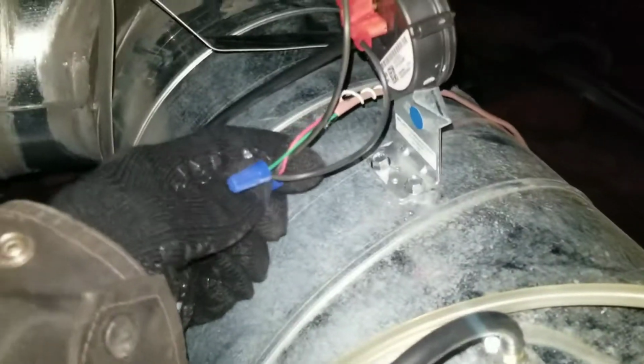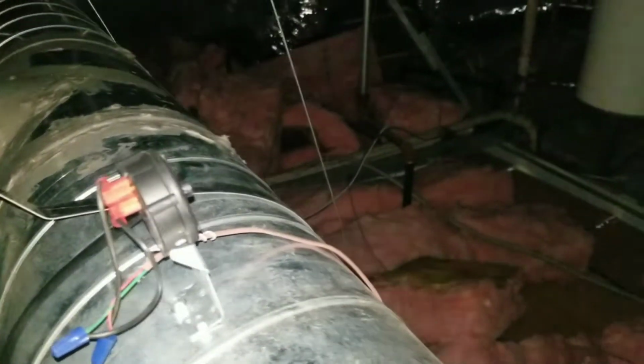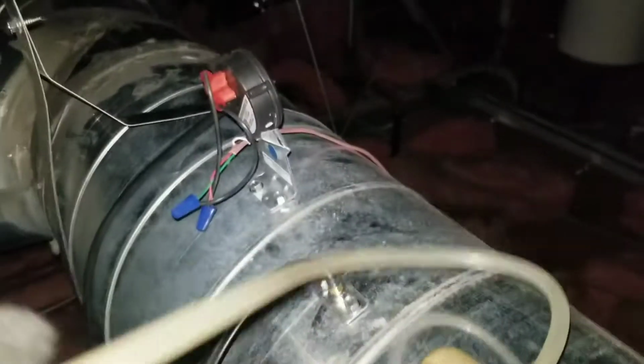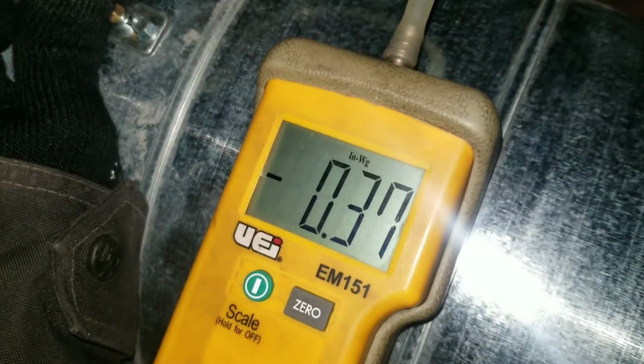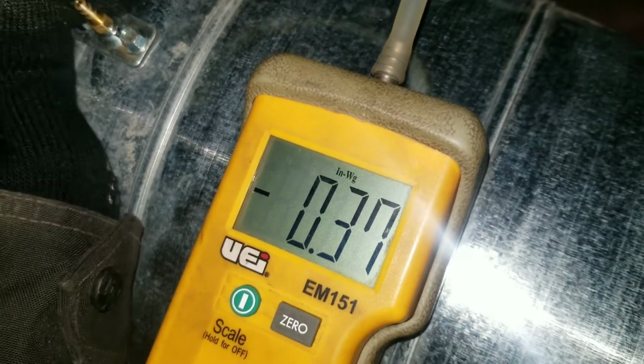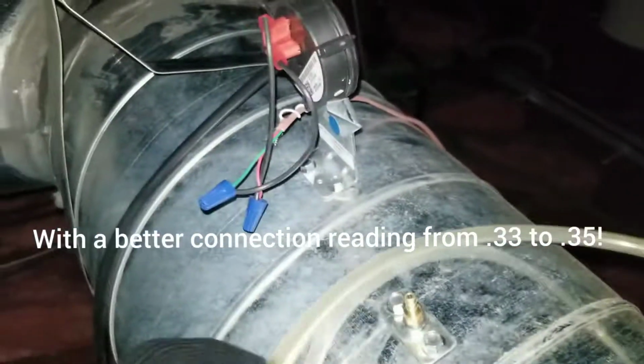So basically we're just closing this pressure switch and sending a run signal to R and G, or we're supposed to be closing this pressure switch. First thing I found was it's not closing. So I am drawing a negative 0.37. And I'm negative 0.35 on my pressure switch. It's just not quite enough to close my switch.